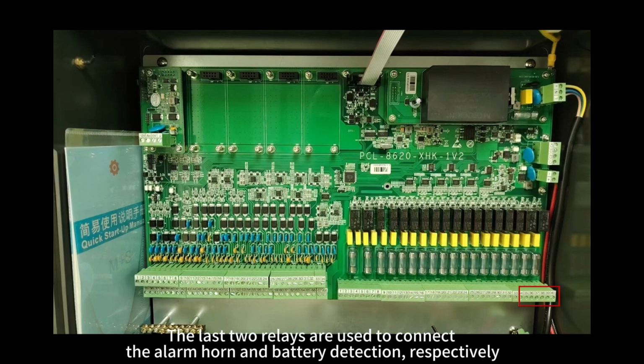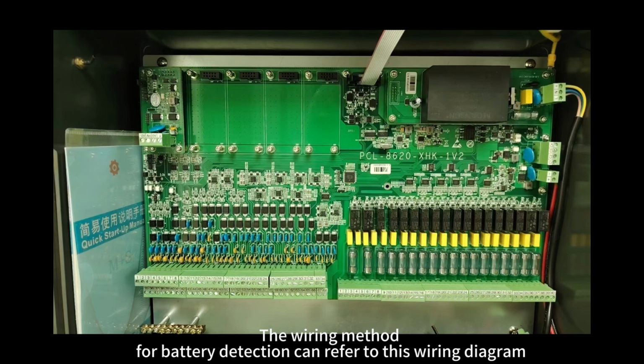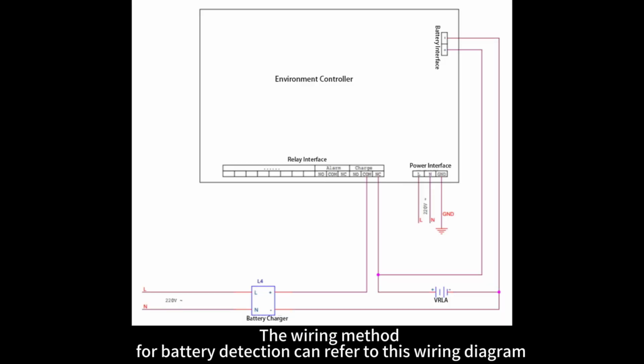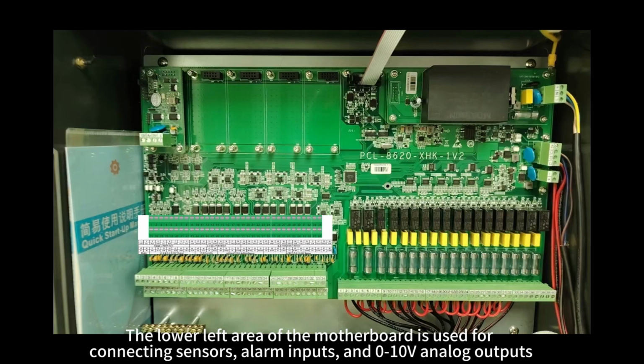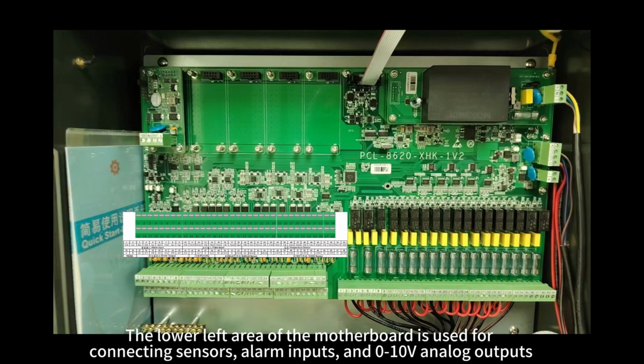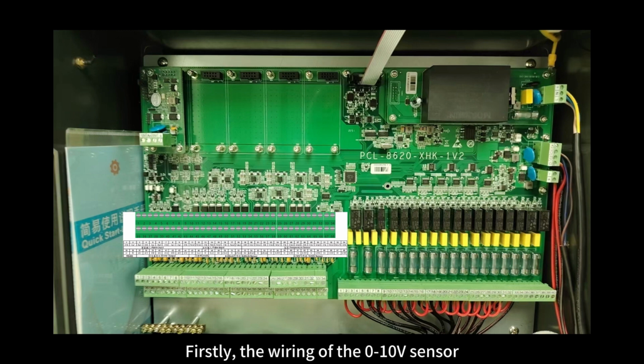The last 2 relays are used to connect the alarm horn and battery detection, respectively. The wiring method for battery detection can refer to this wiring diagram. The lower left area of the motherboard is used for connecting sensors, alarm inputs, and 0 to 10 volts analog outputs. Let's start wiring. Firstly, the wiring of the 0 to 10 volts sensor.